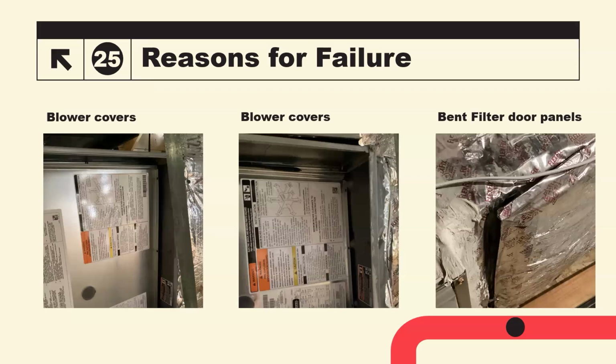And then the last thing, I don't have a picture of it, but heat pumps. It's just a big air handler. The electrician usually has to remove part of that panel to install the wires into the breaker on those heat pumps. It rarely gets screwed back on, and a lot of times the screws are just gone. They're just missing. They're not there.